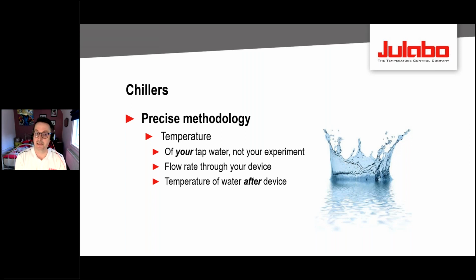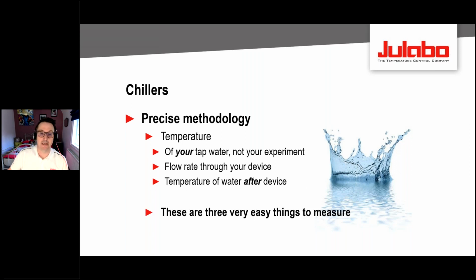What I'm talking about is the temperature of your tap water. The 3 things we need to know are the temperature of your tap water before and after the experiment, and the flow rate through your device. From that we can calculate the power. So measure: the temperature of water going in, the flow rate through your device, and the temperature of the water after the device - from that we calculate the power used.